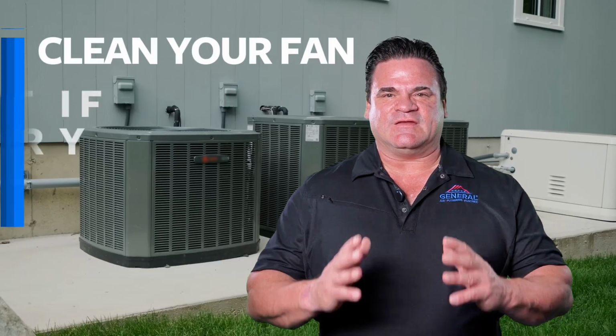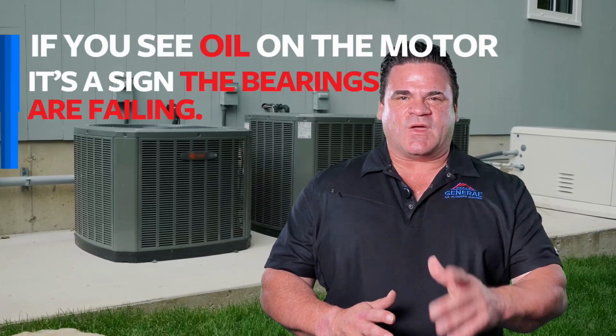Get that fan clean, replace it if necessary. Same thing with the motor. You're looking for, on the motor, any signs of oil that is telling you your bearings on that motor are failing. Stuff you can do on your own if you're slightly handy, stuff you can check out to make sure your system's operating as it should and will operate for many years trouble-free.